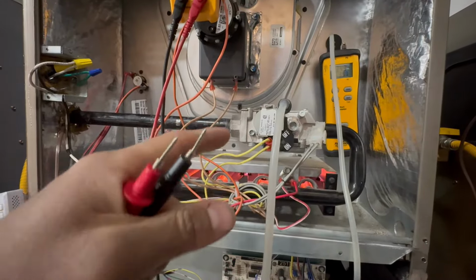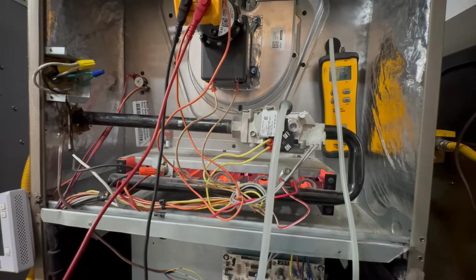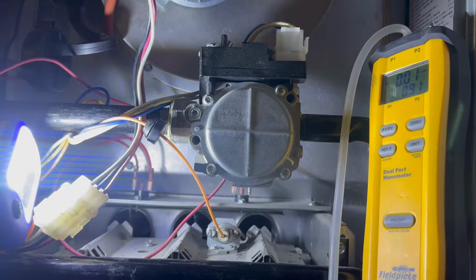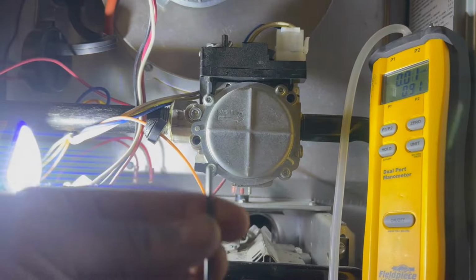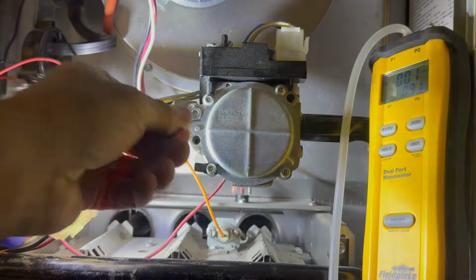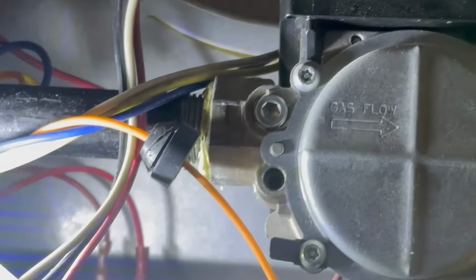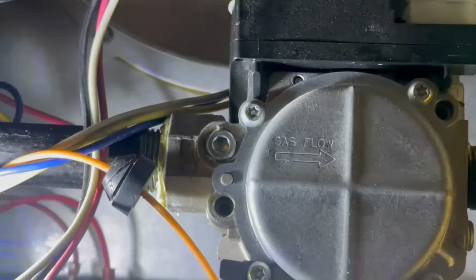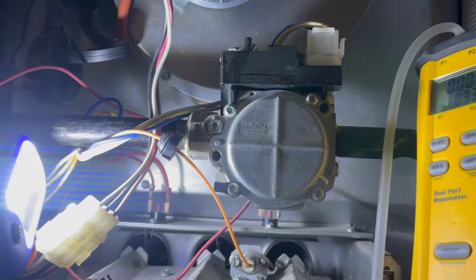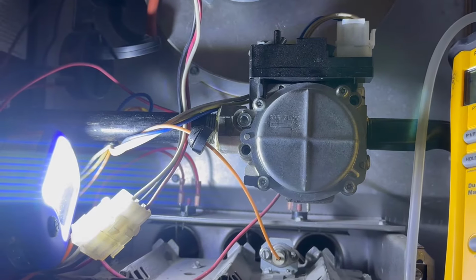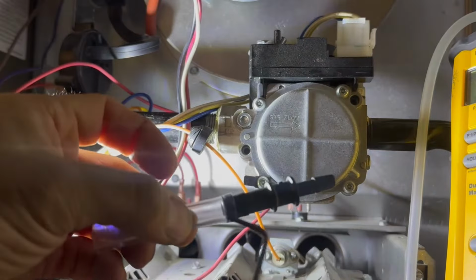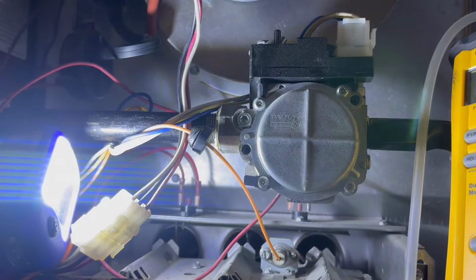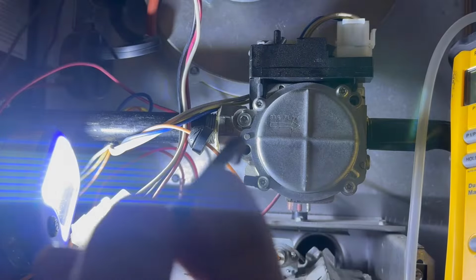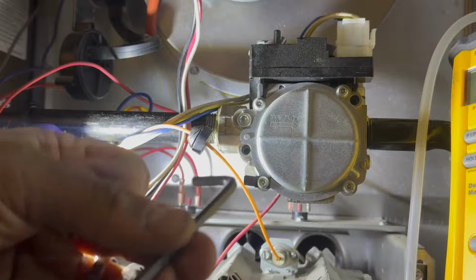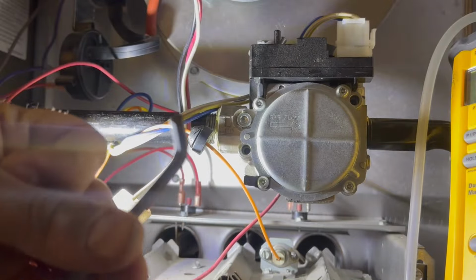Now I'm going to show you how to check another type of gas valve that you'll see out in the field. Okay, so the other gas valve, you needed an Allen key about this small to open the little nut. But this one here is a little bit different. It's a little bit bigger. And you need a different fitting or adapter to be able to read the gas pressure. But I'll show you guys right now. In this one here, you do not need the small Allen key and the piece that we used in the other gas valve. You're going to need this bigger Allen key, right? If you have an Allen key set, I can't recall right now which one it is, but one of the ones on your Allen key set will fit there.